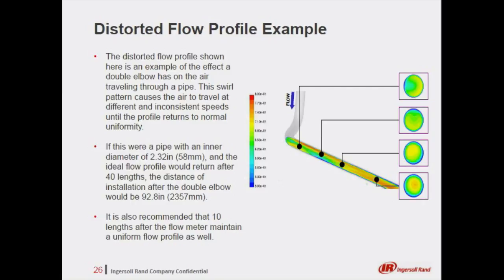In this example, with a double elbow, we can expect the flow profile to return to normal after 40 lengths of pipe and would recommend 10 lengths after the flow meter. If the pipe's inner diameter is 58 millimeters, the distance of installation after the double elbow would be 2,357 millimeters, or about 8 feet, and 1.5 to 2 feet after the flow meter.